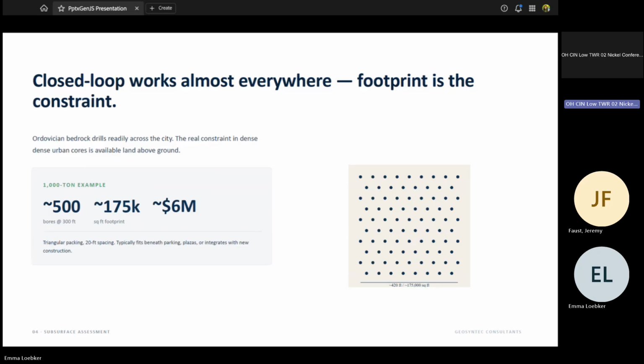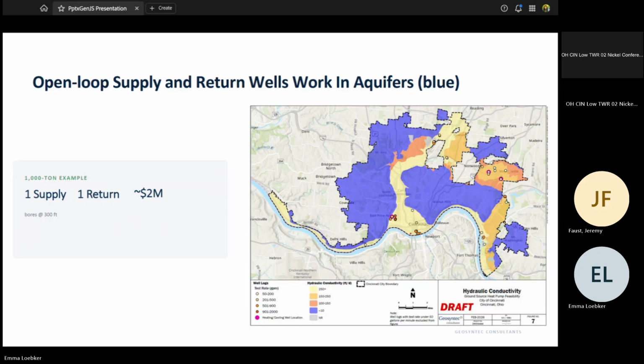Whereas an open loop or in-well heat exchange system, to get that same 1,000-ton capacity — apples to apples comparison — you might need one supply well and one return well in this kind of geologic condition, and that could be around $2 million. Don't take those numbers to the bank — they're site specific and highly dependent on geology — but it gives you a sense of scale: aquifer-based systems tend to scale a lot better in terms of costs.